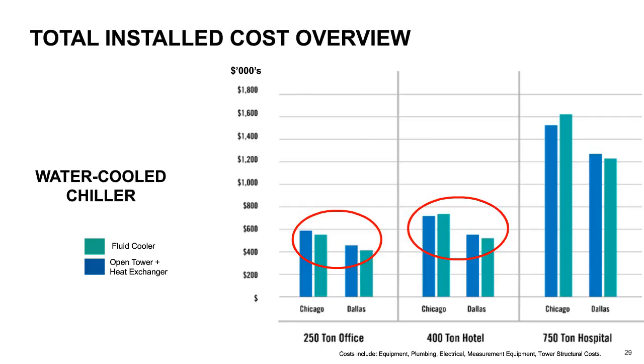For the 400-ton hotel case in Chicago, the fluid cooler was a little more costly than the tower heat exchanger. However, in Dallas, it was less costly. The 750-ton hospital case, you can see that the fluid cooler was quite a bit more expensive than the tower heat exchanger option. And in Dallas, the fluid cooler was again lower cost.